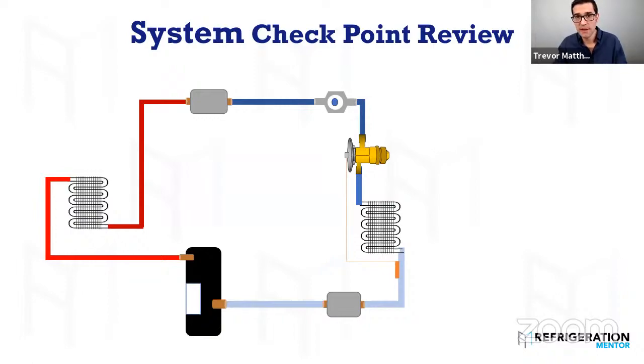This is your job. And when you start doing these checkpoints, you can tell any refrigeration expert the checkpoints you check, and they'll be able to tell you what's going on, because they can see what's going on inside the system, and they know the numbers. When you know the numbers, you know what's happening. And this is from refrigerant temperatures, pressures, and electrics, amps, volts. When you know all that stuff, it's easy. Your troubleshooting gets a lot easier.